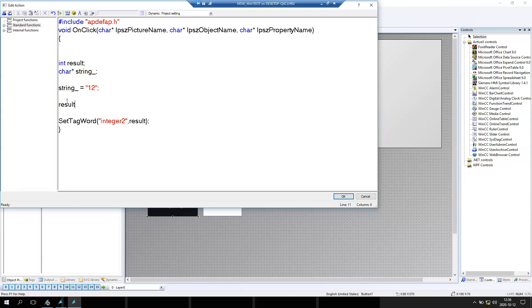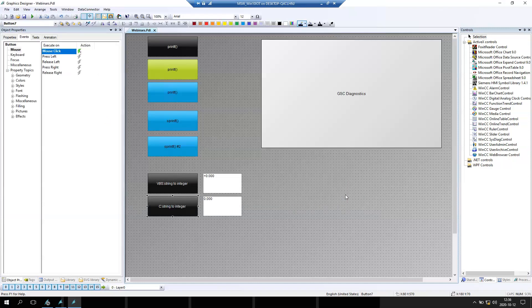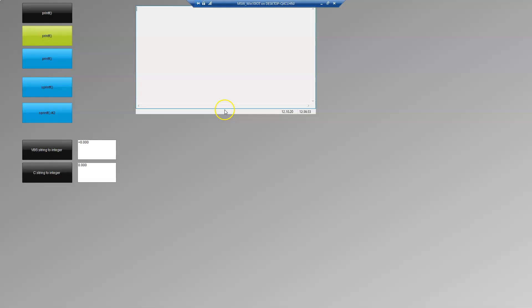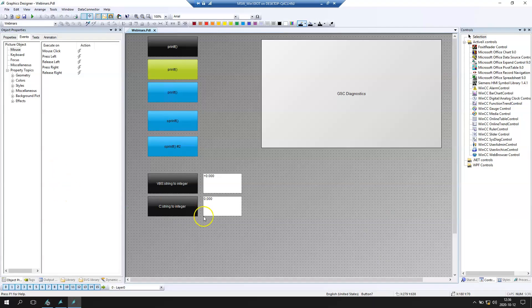So we see the same like in Visual Basic Script. And our result is the function. Function atoi is function built into C WinCC library where we can transfer data from string into integer. After we put WinCC runtime again and we click the button, the value is transferring into output of integer into 12.